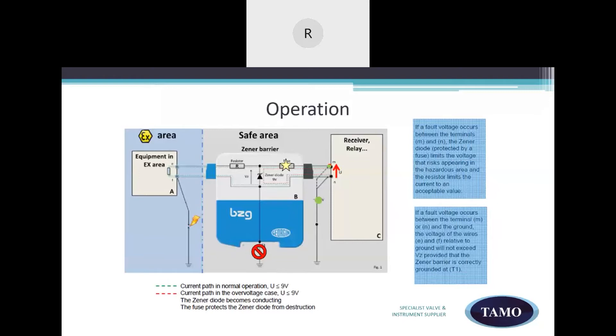It is very important that the Zener is properly grounded. When a Zener diode conducts as a result of overvoltage, the fuse will protect the Zener diode due to the overcurrent during conduction. The Zener barrier will also allow a short circuit between the supply terminals and the intrinsically safe device installed in the hazardous location without creating a spark which may be dangerous. In case of any short circuit, the resistor limits the current to an acceptable value which will not be sufficient to create a dangerous spark provided that the Zener barrier is correctly connected to ground.